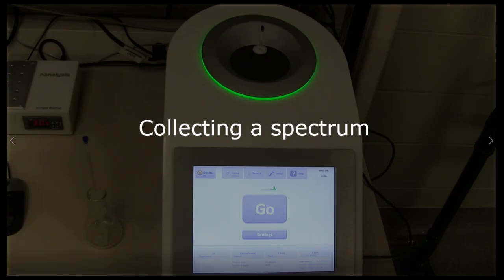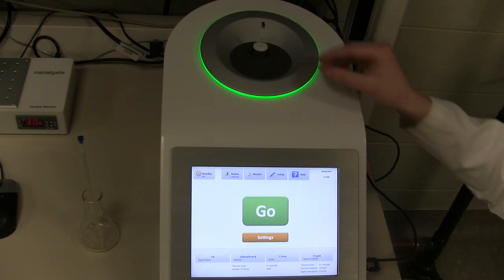This portion of the video will go over how to take an NMR spectrum with the 60 MHz NMR spectrometer. Take the NMR out of standby mode with the upper left button and remove the reference tube.